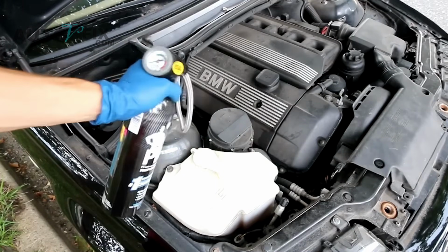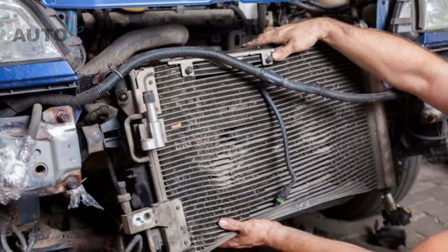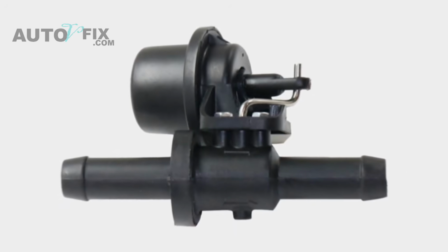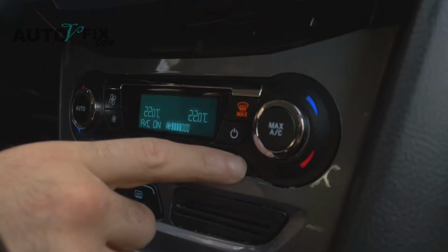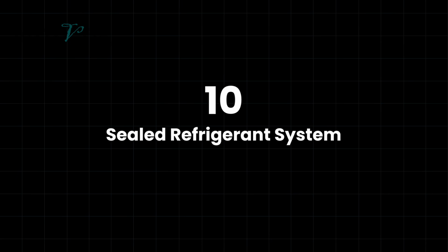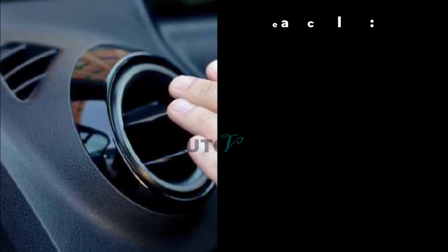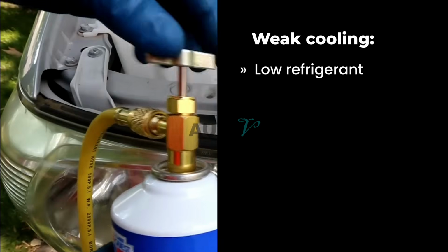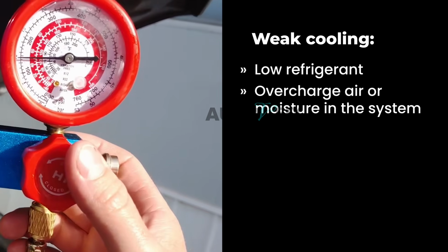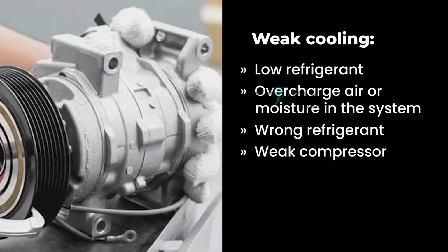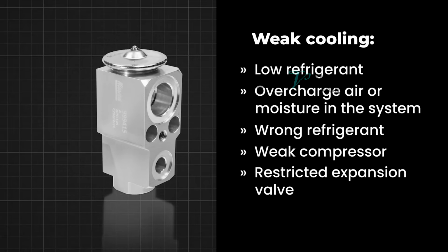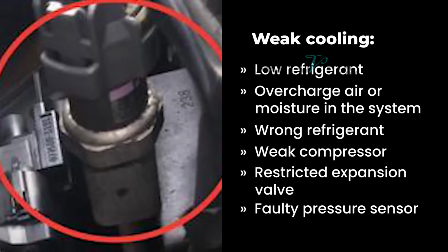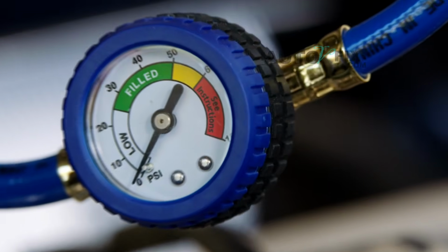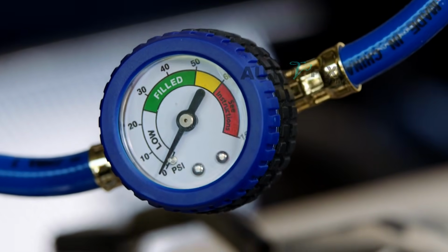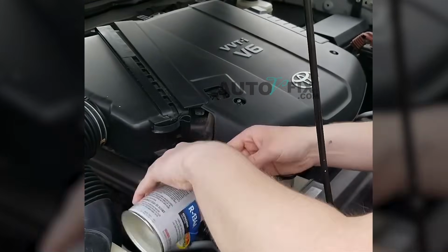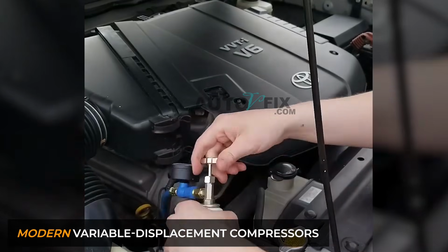Do not replace the sensor based on one reading alone, but use that clue before spending money on refrigerant or a compressor. Now, if all the airflow, condenser, door, drain, and sensor checks pass, then it is time to look deeper into the sealed refrigerant system. This is where you need to be careful. Weak cooling can be caused by low refrigerant, overcharge, air or moisture in the system, the wrong refrigerant, a weak compressor, a restricted expansion valve or orifice tube, a faulty pressure sensor, or a control problem. A single low-side gauge on a recharge can cannot accurately separate all of these issues, especially on modern variable displacement compressors.